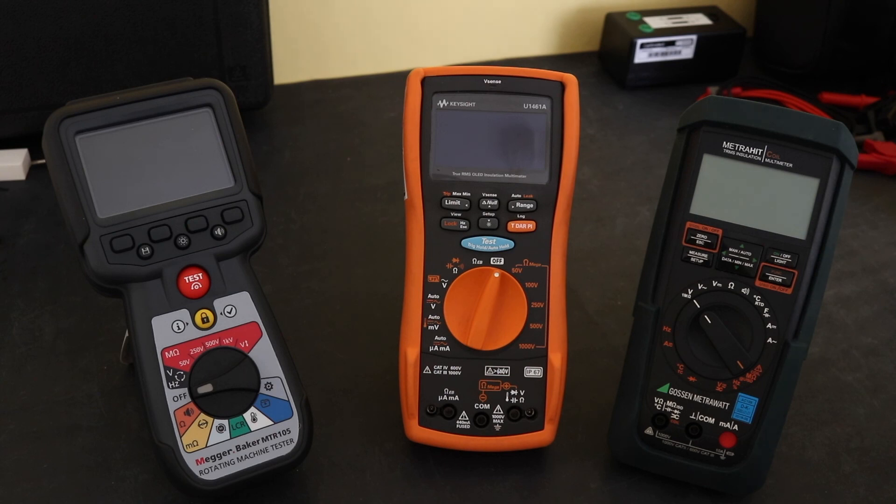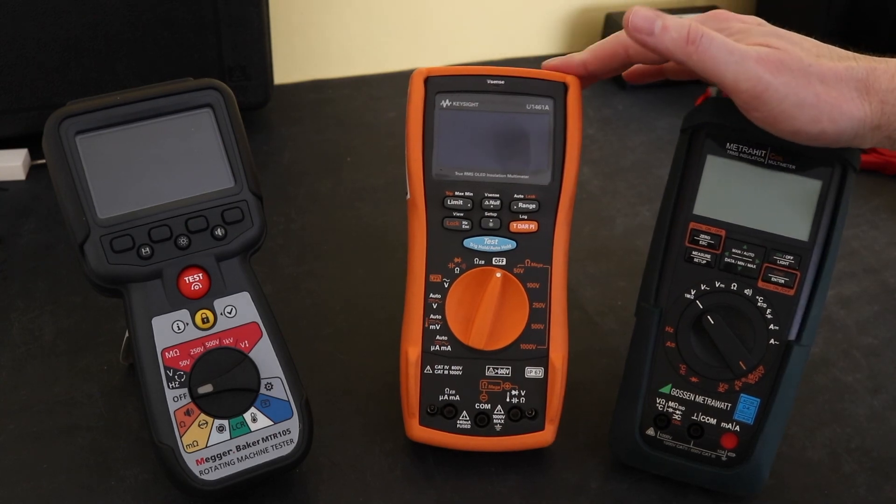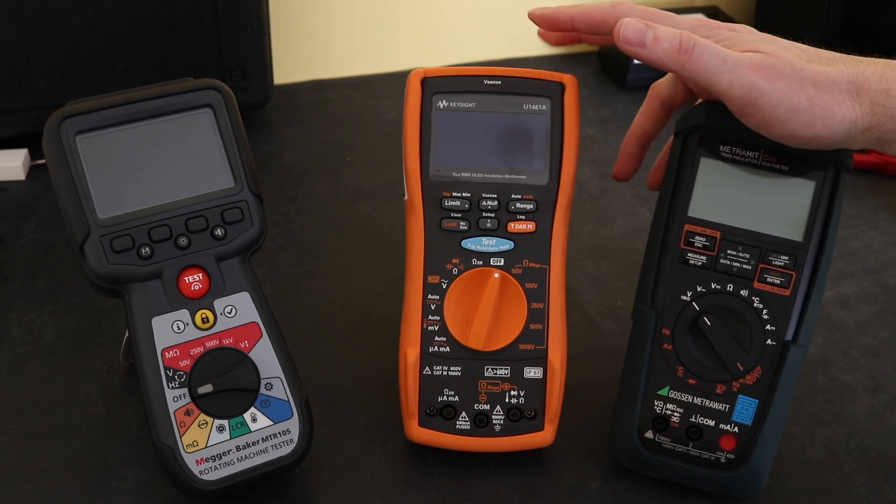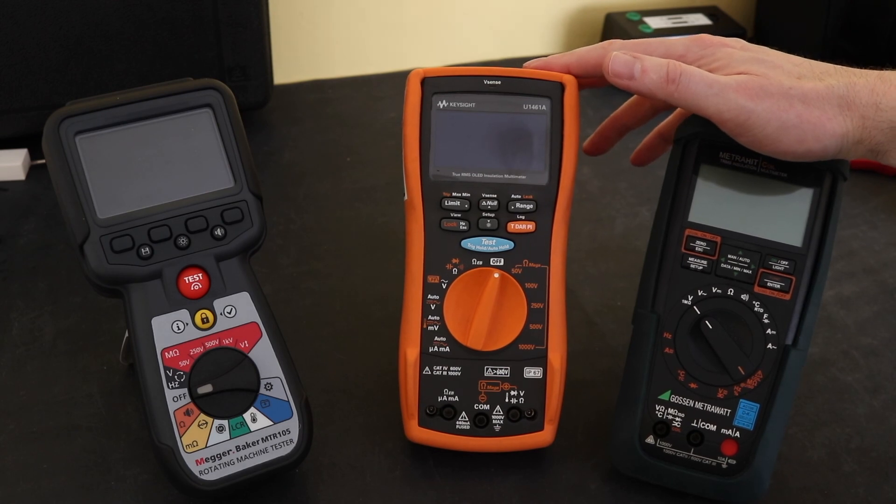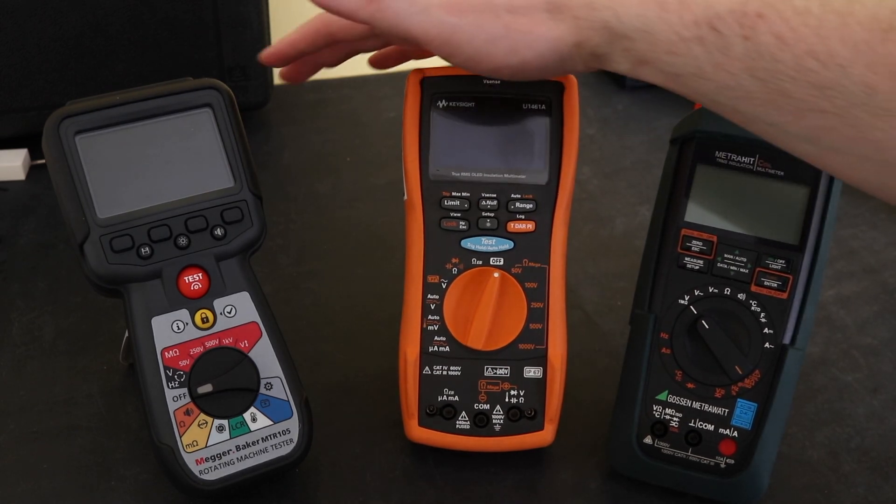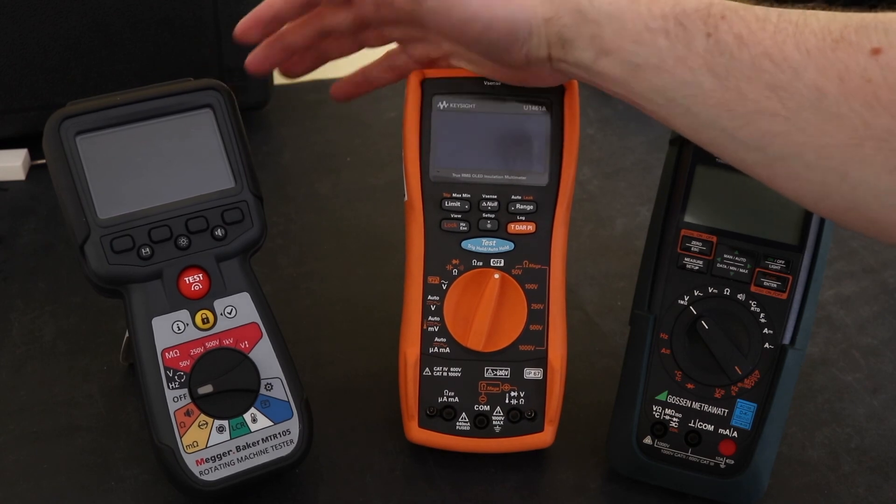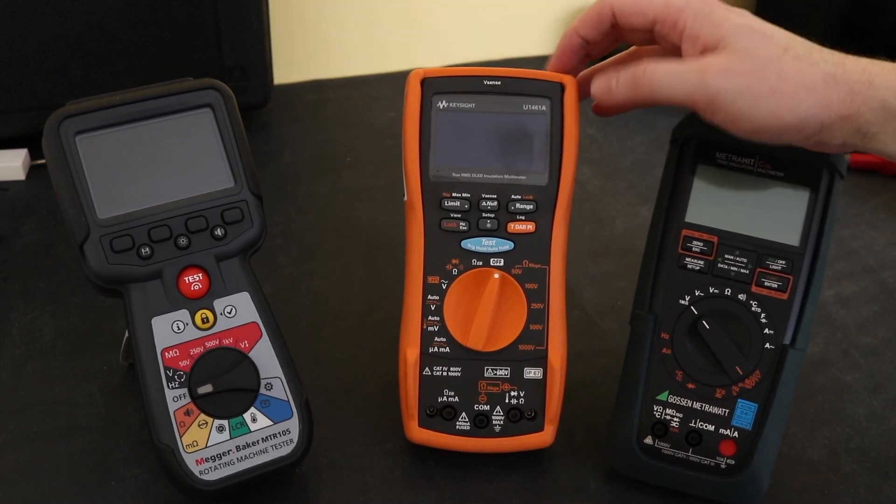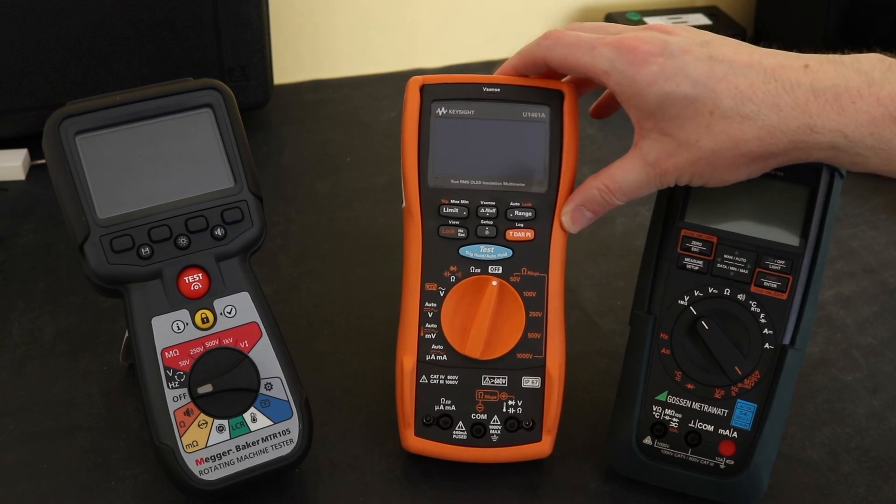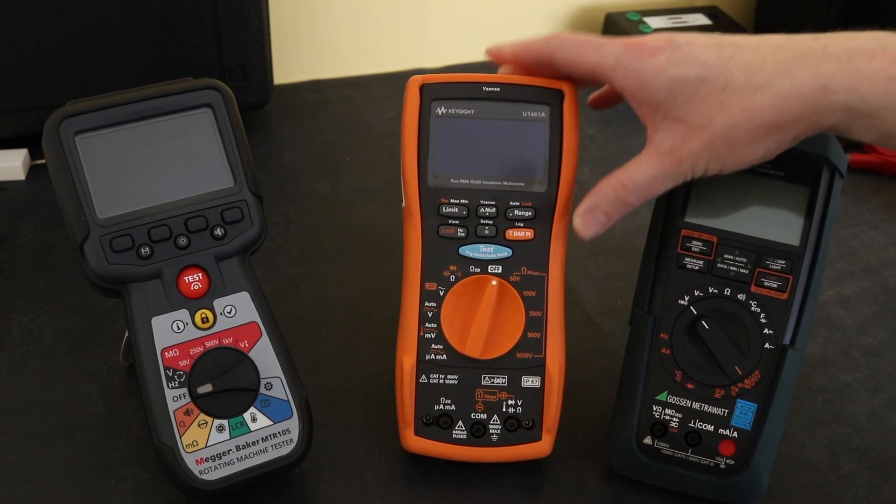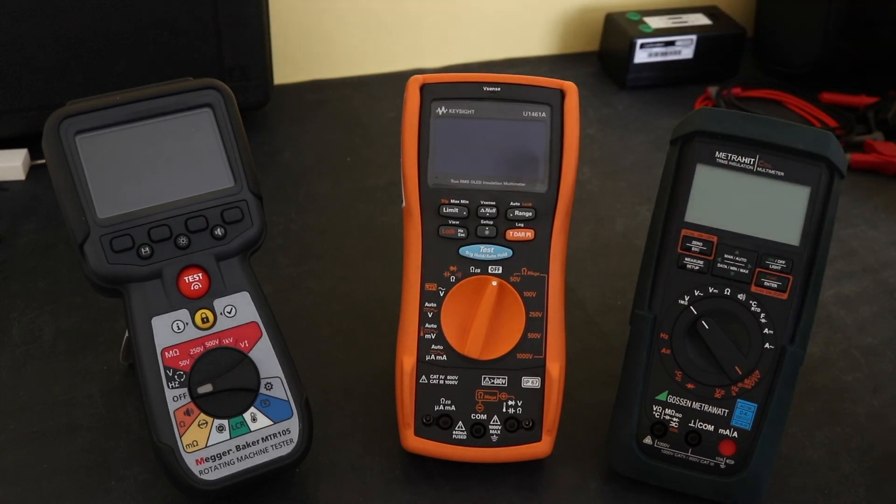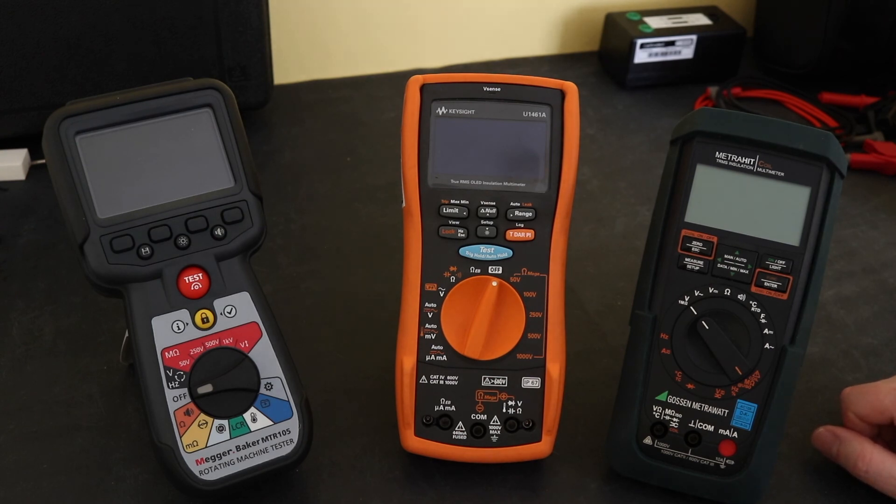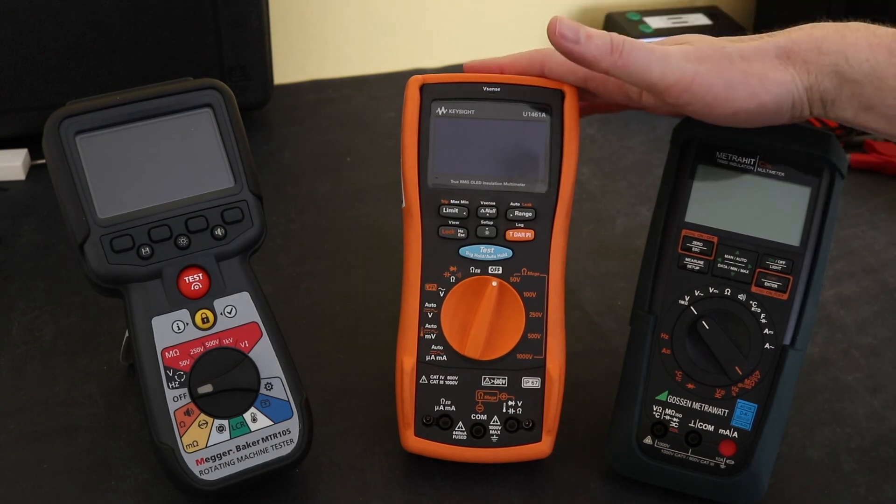First and second, I think in actual fact based on the overall figures I'm going to give first place and five points to the Keysight unit. It is that little bit more accurate and it passes all the other tests. They're quite comparable to the actual results that seen on this one. I also do tend to like you get a better response from the display on this as its insulation value is increasing or decreasing whereas this seems to be a much more stepped output that isn't quite as effective as the one you see on the Keysight unit. So yeah, first place five points.